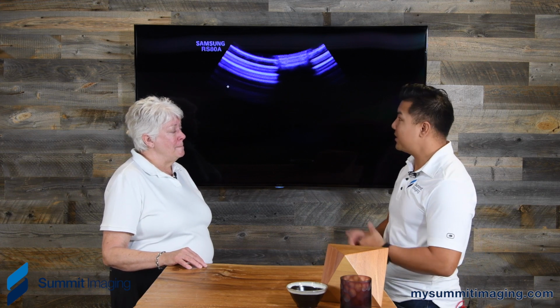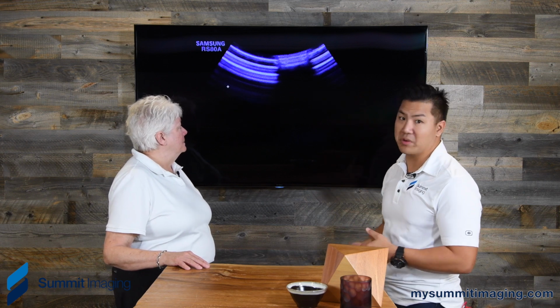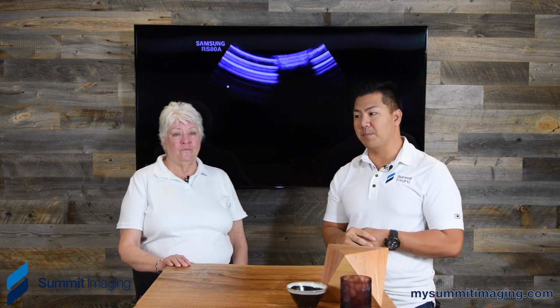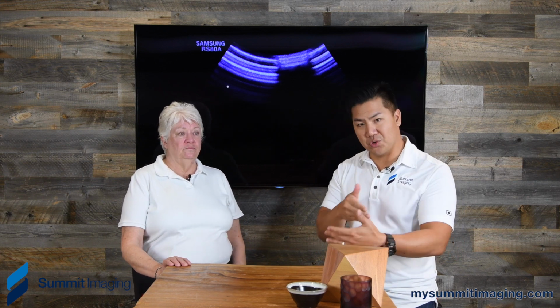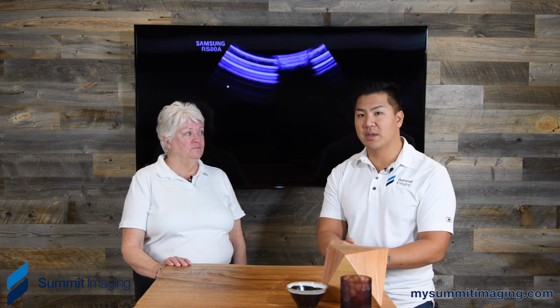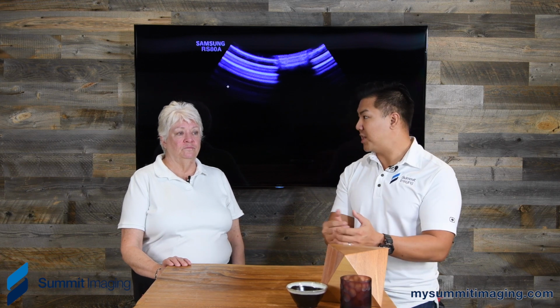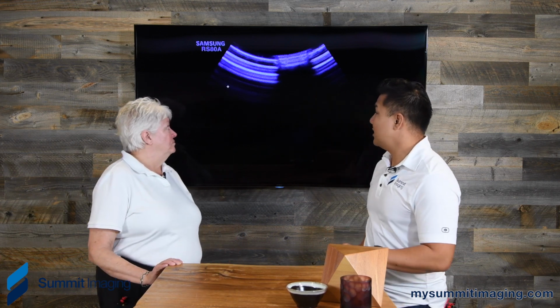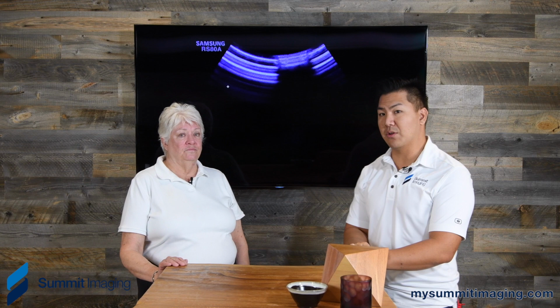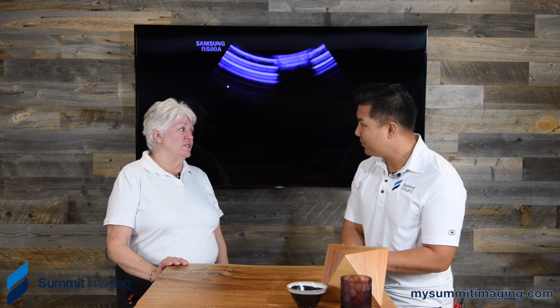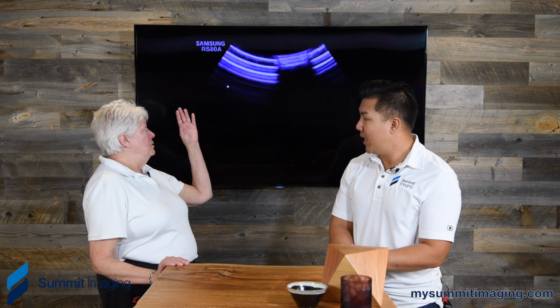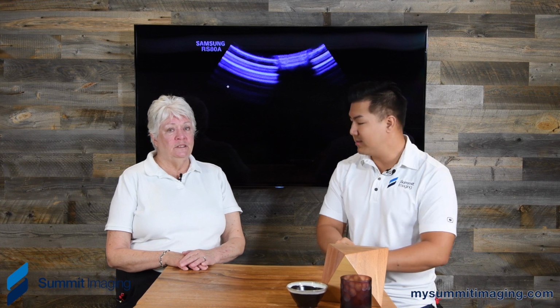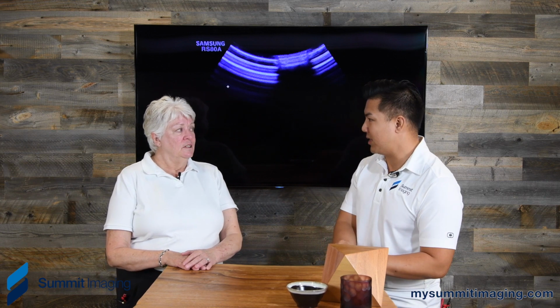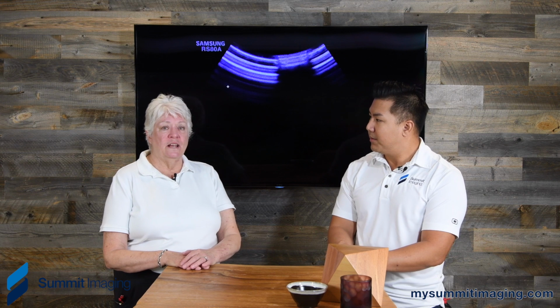But from what we see, for the most part, there is definitely some sort of impact that has occurred to compromise the seals, and then the oil leaves the cavity that it's supposed to stay in, and is replaced by air. This is a catastrophic issue for image quality, but a very common issue for mechanical volumetric transducers. And it's time consuming for the sonographer to troubleshoot. And it's messy too. We've had probes come in where there's oil all over the box. It's a messy proposition. It takes a long time to clean up and make sure it's right. And it impacts the quality of the exam.